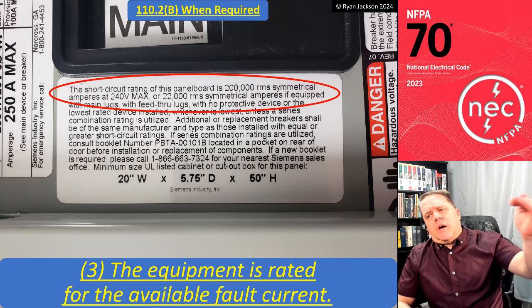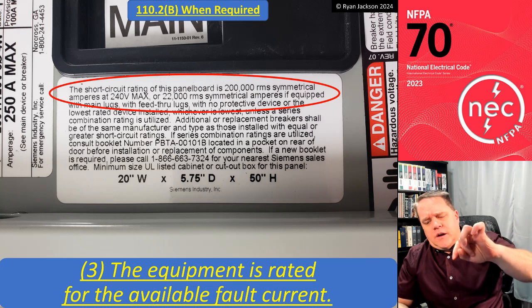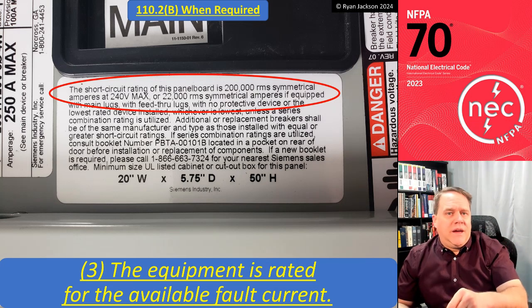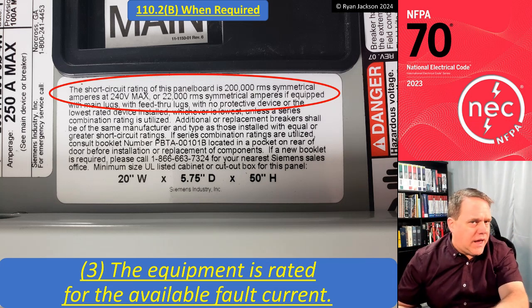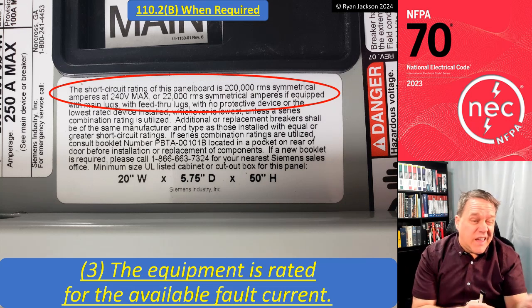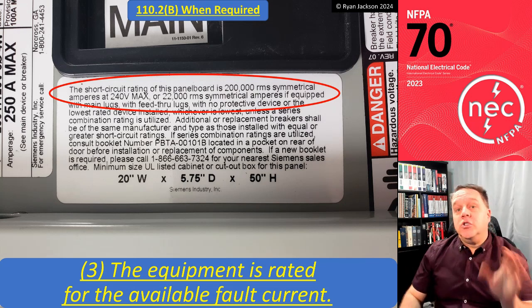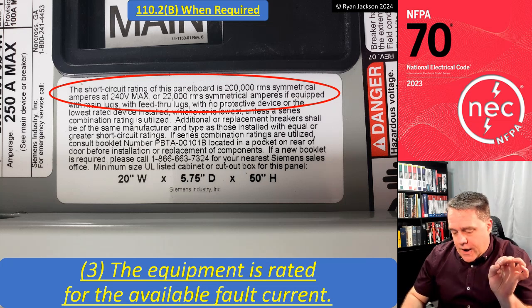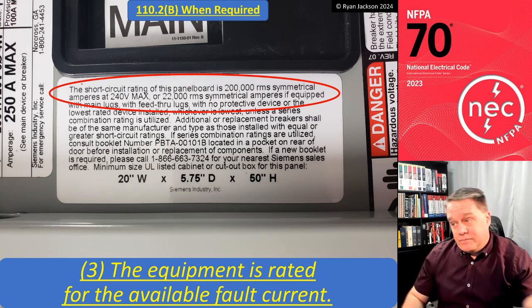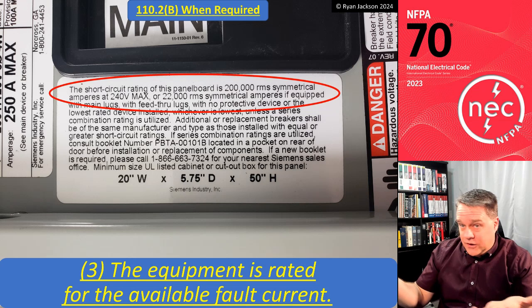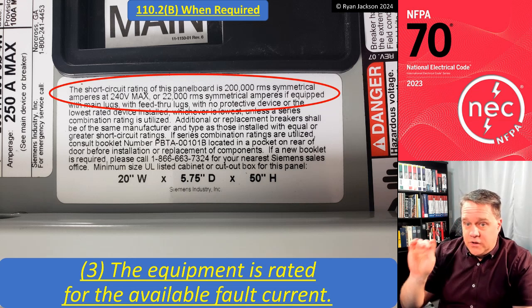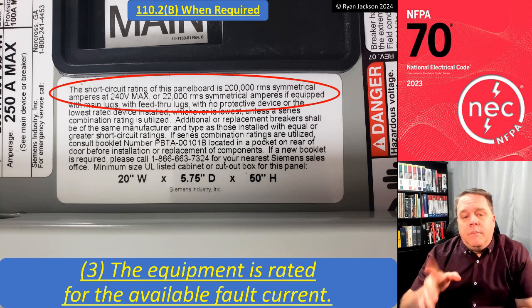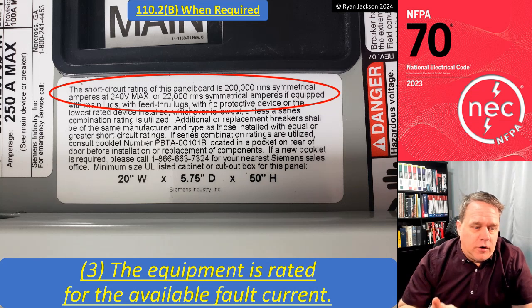If this was coming straight out of a transformer and it went main lug, which normally we can't do that. There are instances where you can if you look in the NEC, but usually you cannot do that. If you were able to, though, the available fault current or the short circuit current rating, not 200,000, it's only 22,000. So make sure everything is rated for the available fault current.